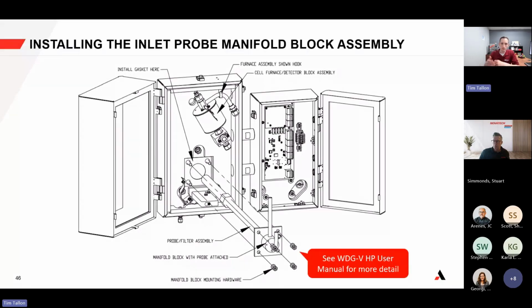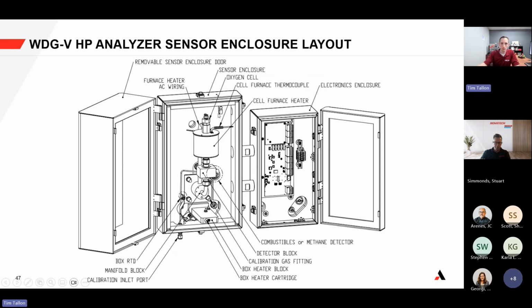And then after you clean the filter and clean the probe and you put on a new one, you can reinstall it by reattaching it, sliding right back into the assembly. And as you can see, the furnace is still hanging here, and you can rebolt with easier access. So that's one way to make it easier to access the probe and filter, and also easier to reinstall without having to disconnect everything. So how'd I do? Is that helpful? Is that a good answer?